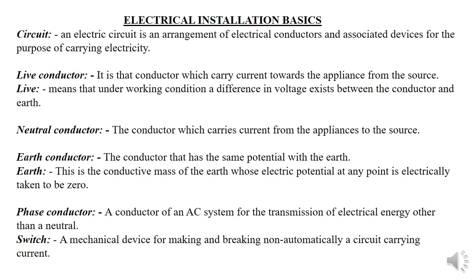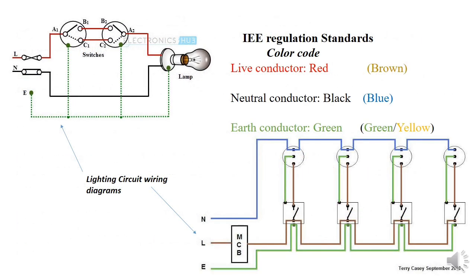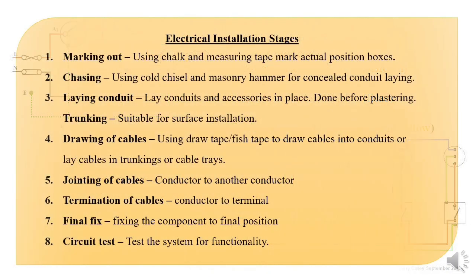The earth ensures there is no excess current going to the circuit — it disposes of excess current. You also need to understand the color codes. In Kenya we use British Standards guided by the IEE Regulations: red for the live, black for the neutral, and green with yellow stripes for the earth. In other countries like Germany they use brown for the live, blue for the neutral, and yellow-green for the earth.